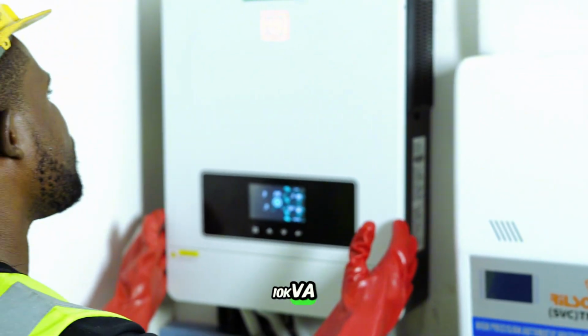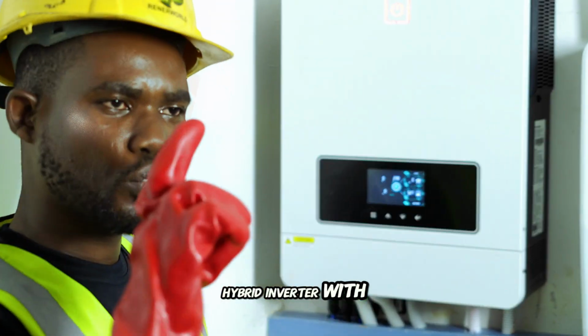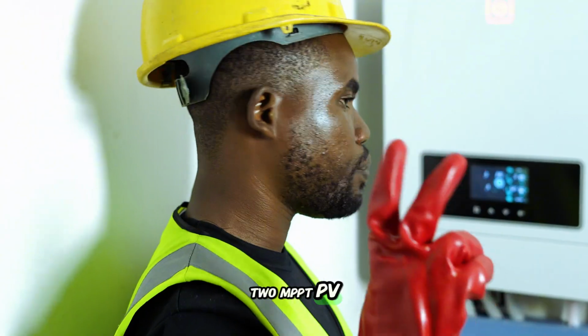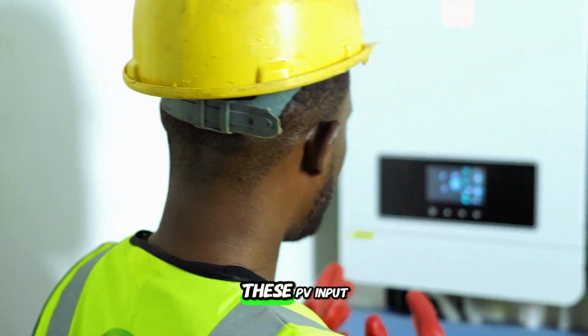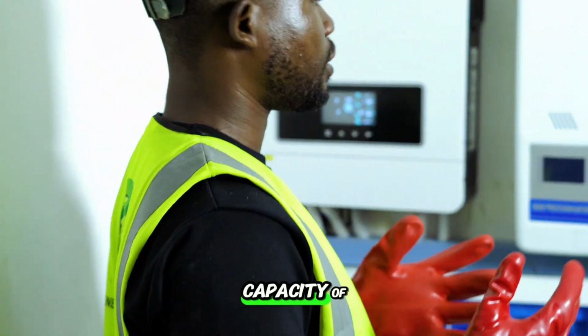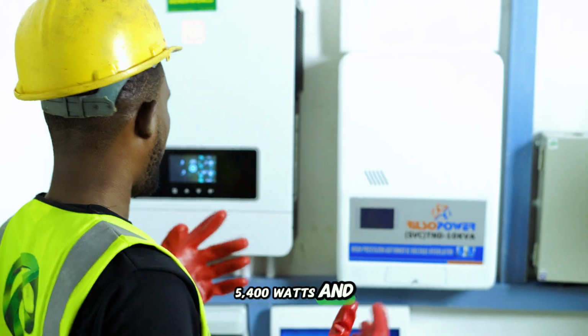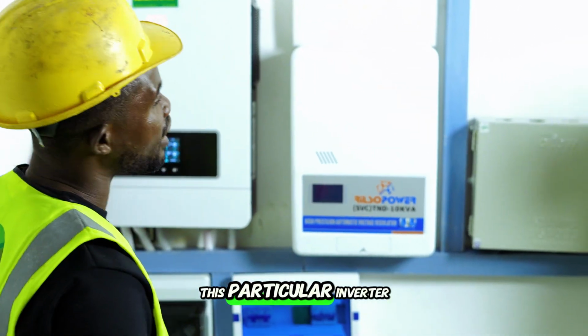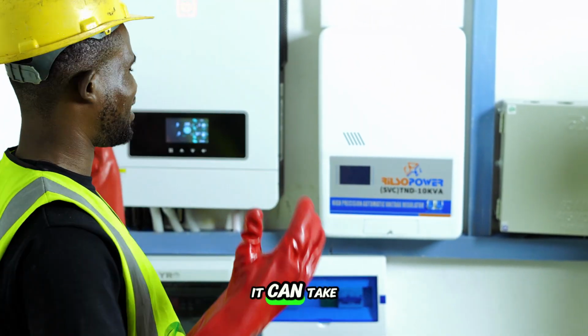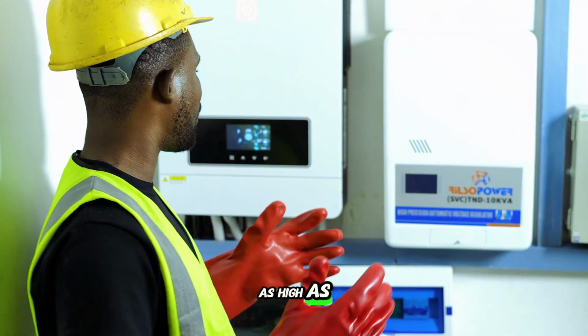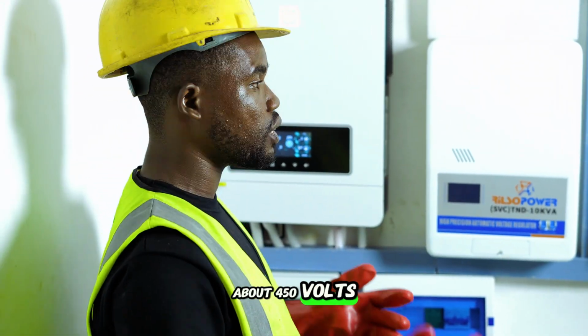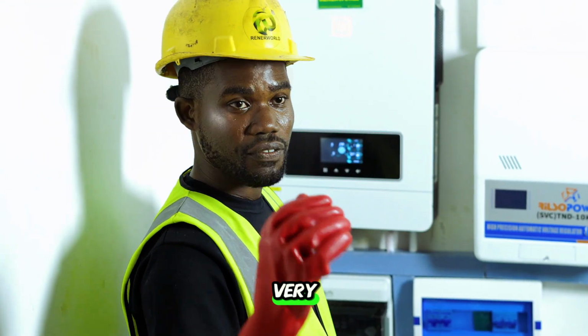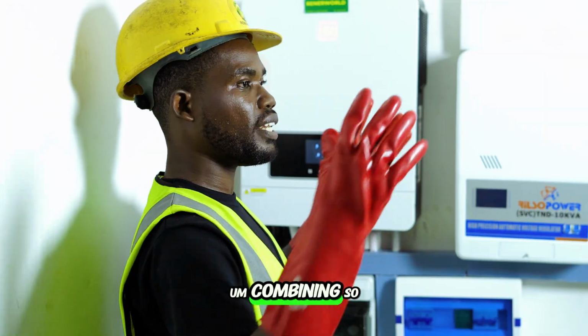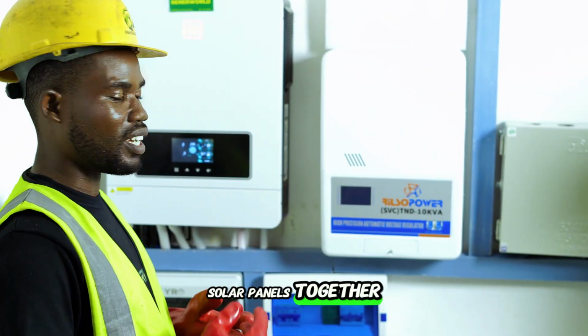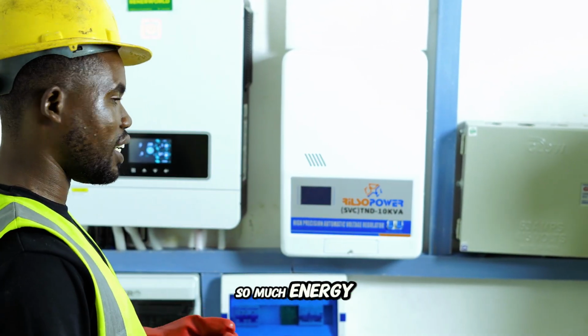We have this 10 kVA hybrid inverter with 2 MPPT PV inputs, and each of these PV inputs comes with a capacity of 5,400 watt. It is good to note that this particular inverter is a high voltage inverter. It can take as high as about 450 volt PV input, which makes it very suitable for combining so much solar panels together, and helps you bring in so much energy.